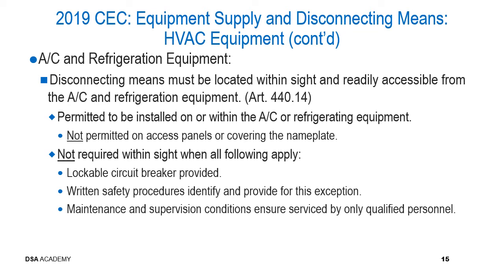We'll talk now briefly about some air conditioning and refrigeration equipment, specifically the disconnecting means required for these pieces of equipment. The disconnecting means must be located within sight and readily accessible from AC, air conditioning, and refrigeration equipment. This is stipulated in Article 440.14. The disconnect is permitted to be installed on or within the air conditioning or refrigeration equipment. However, it is not permitted on access panels, and it is also not permitted to cover the nameplate. Obviously, right?